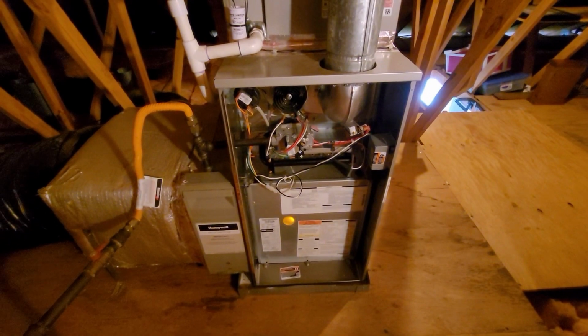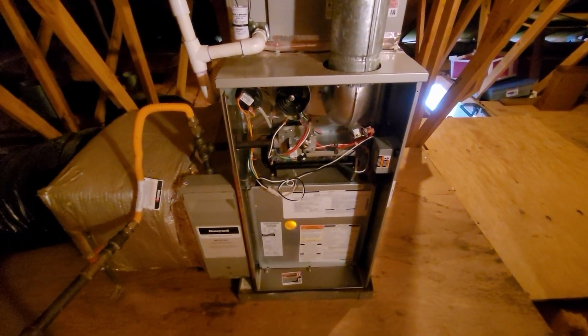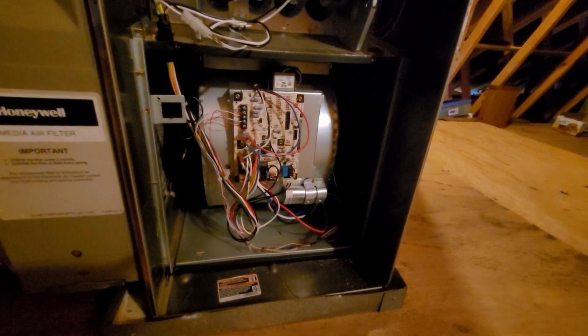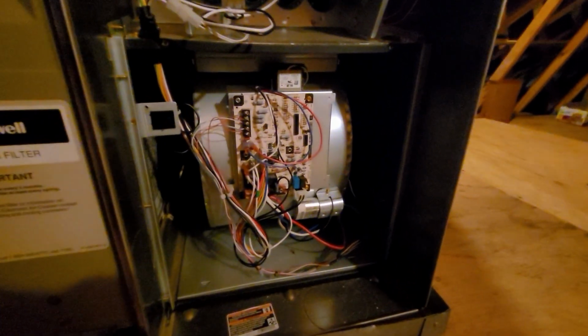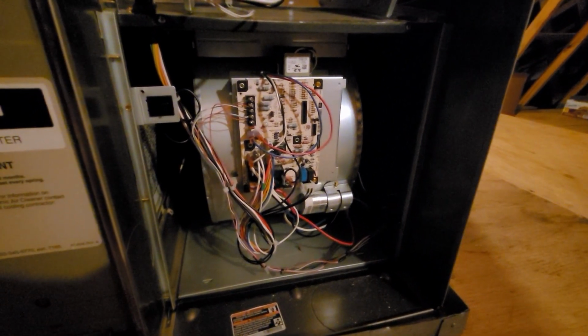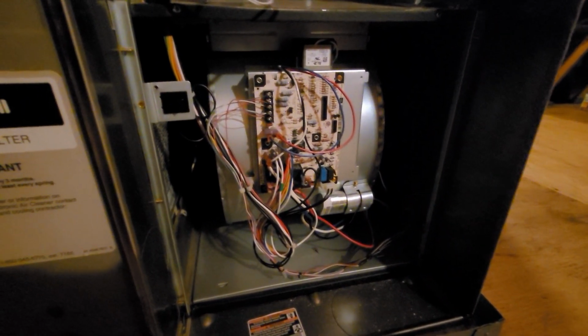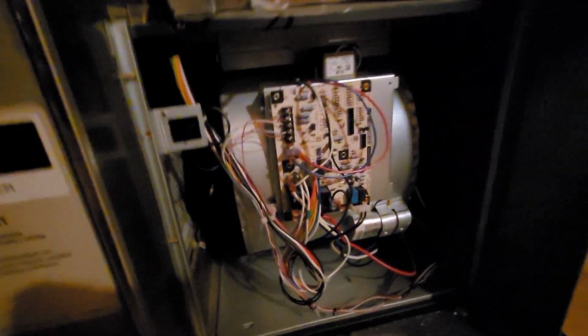Look at it again. I have removed the front cover. I have now removed the panel exposing the wiring, and the unit automatically shuts off because when you remove the cover, it lets go of this safety switch, which does not allow the unit to run when the cover is off the panel. Now over here you could see a series of wires, and on the bottom you could see a red wire. This red wire is the 24-volt wire that hooks up to the thermostat, which controls both the heating and the air conditioning.